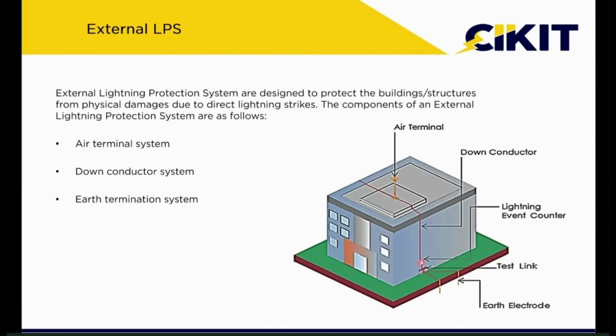So if you take the external lightning protection system, there are three main components: the first is the air terminal, the second is the down conductor, and the third is earthing. The air terminal is the component which intercepts the lightning. That is, it is the component which makes contact with the lightning source. So it should have sufficient capacity to withstand the lightning impulse current. At the same time, it should be able to withstand the huge mechanical stress due to heavy wind and so on. So the air terminal should have sufficient mechanical strength as well as electrical strength.